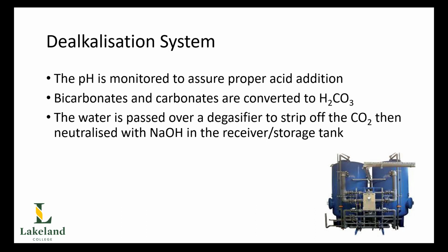Now, the rest of it is going to be addressed because we now have to neutralize this very acidic water that we've got down at the point of free mineral acidity. And we do that by neutralizing it with sodium hydroxide, which of course contains hydroxide alkalinity, and it also thereby raises our pH, and this is done in a receiver or storage tank.